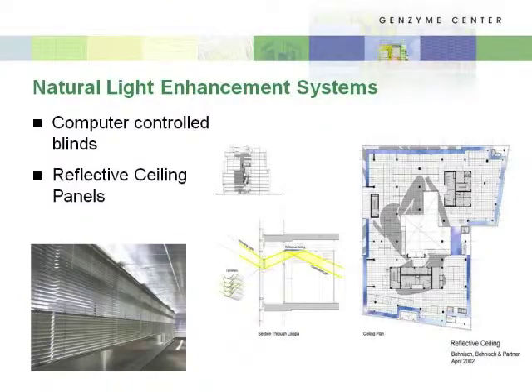The blinds, we have 1,030 of these blinds. They're all based off sunlight: north, south, east, and west. Anything above 59.7 degrees will reflect the sunlight or the heat out, and let the sunlight in. By saying that, we have 2 steam absorption chillers, 480-ton chillers. The building was designed to run both of them at about maybe 50-60%.